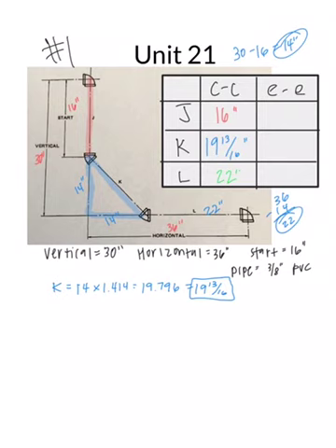Now, I feel like we've been doing a lot with the takeoffs. So if you understand how to do your takeoffs, you can be done watching. But just in case, or if you just want the answers, I'm going to hurry and find each of these end to ends. So starting with pipe J. Pipe J is 16 inches center to center. And pipe J is between a 90 and a 45. And we have 3/8 inch PVC.